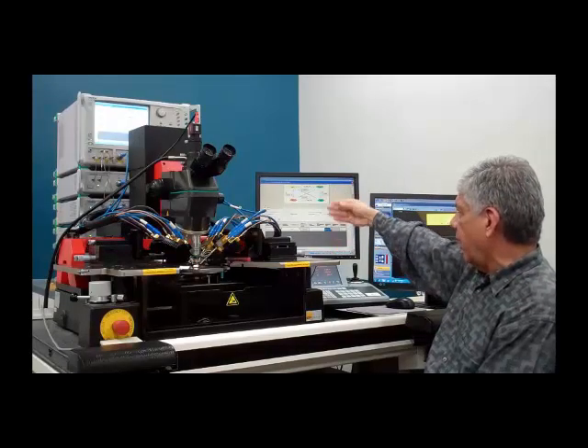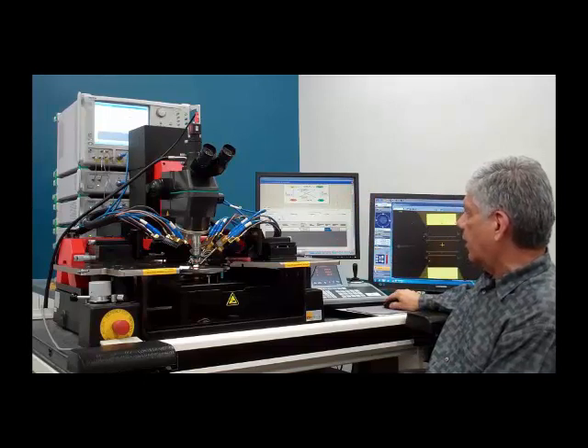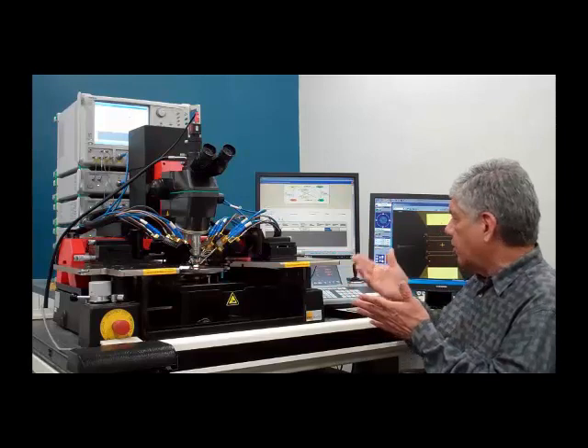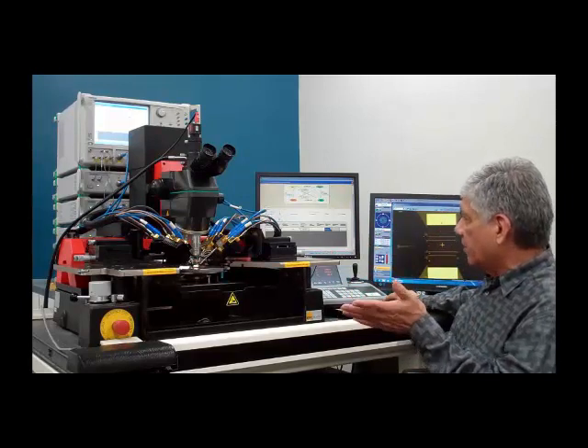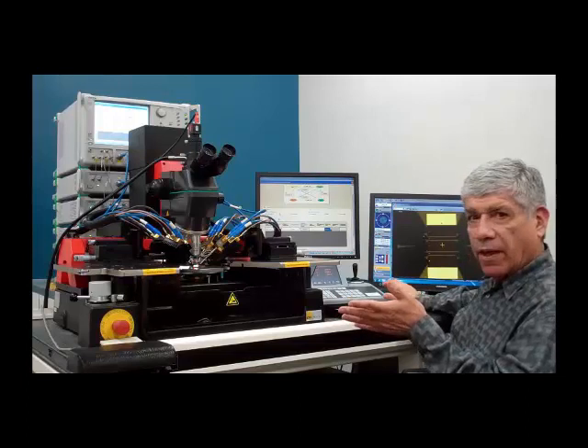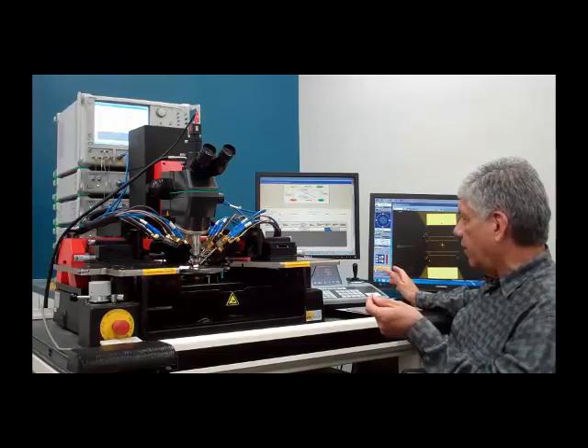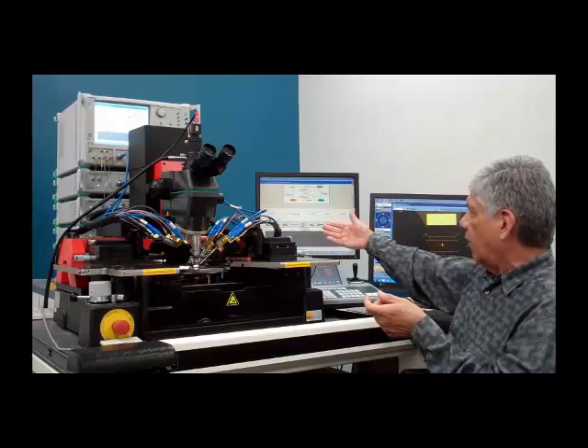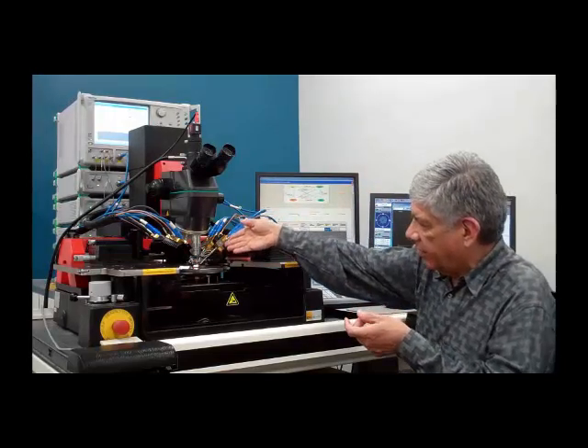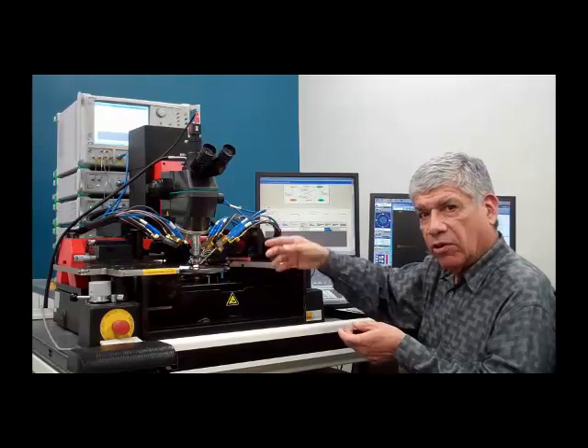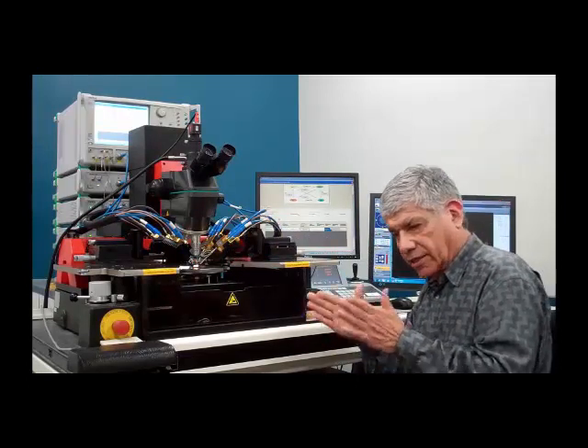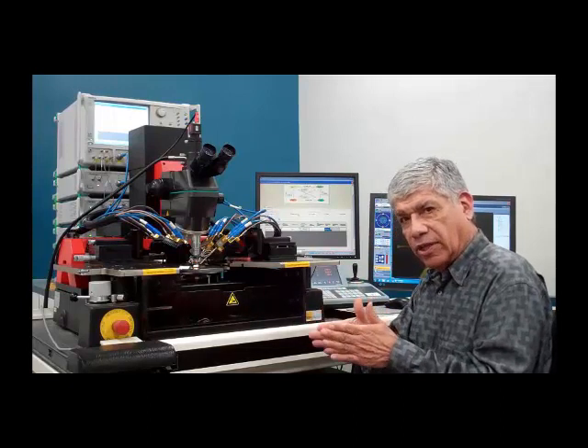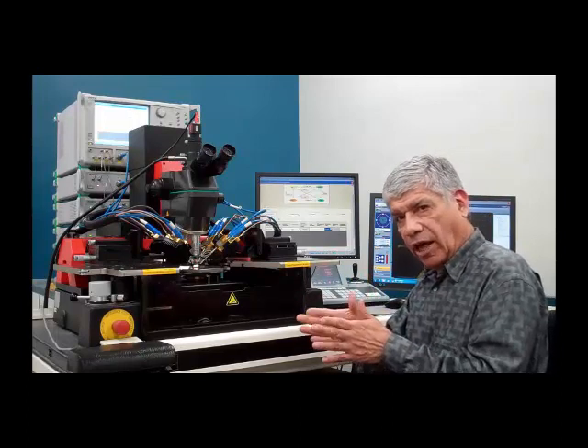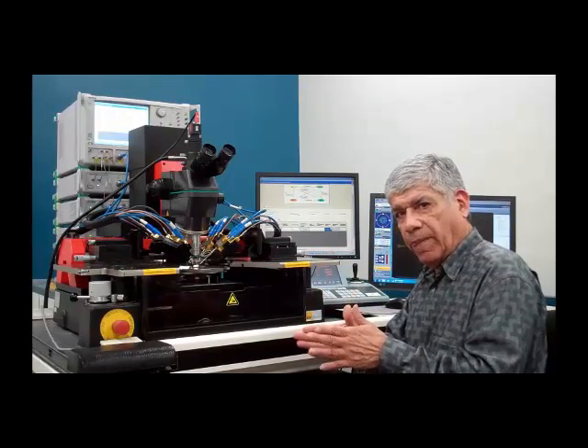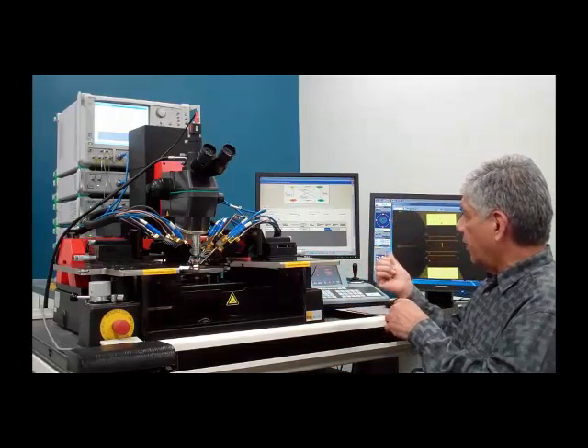And so there's a Cal A, Cal B, but basically what it is, is setting up our calibration in terms of things like, for instance, the reference plane location. We can set it up for end of line, or middle of line. At end of line, we are going to be calibrated at the probe tip itself. In the middle of line, if your line is the same length as the path to the DUT, then you can calibrate using middle of line and have the test port calibrated to the DUT itself. So that's why the choice between end of line and middle of line.